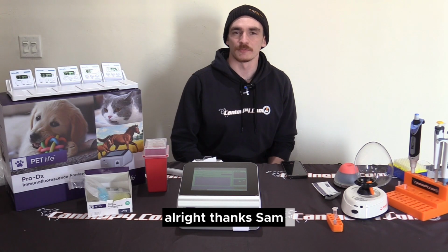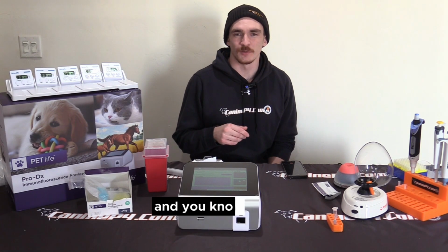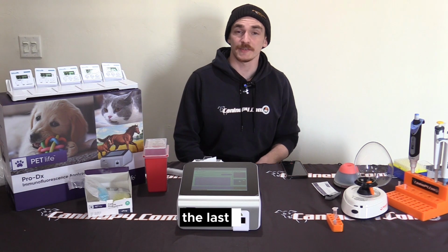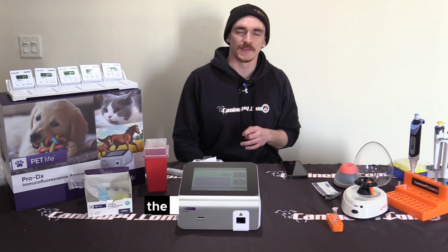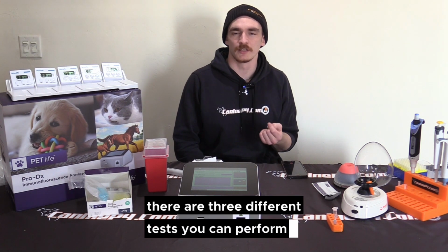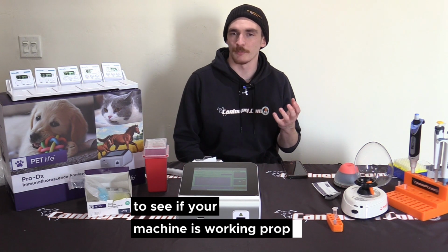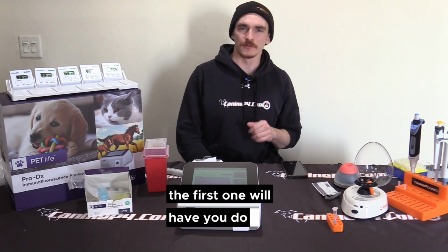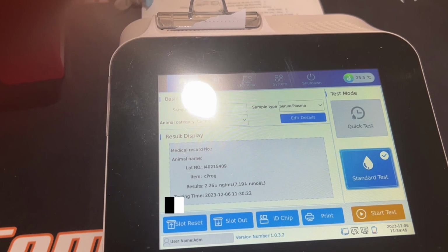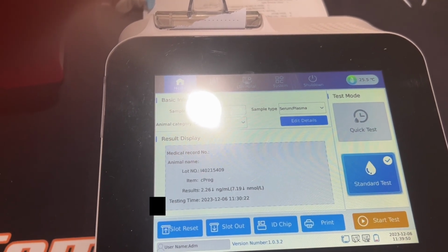All right, thanks, Sam. Now you know what those numbers mean, and you know exactly when to breed. The last thing I'm going to go over here is troubleshooting. There are 3 different tests you can perform to see if your machine is working properly. The first one is the precision test. This test is designed to make sure the machine is reading the same number multiple times in a row.